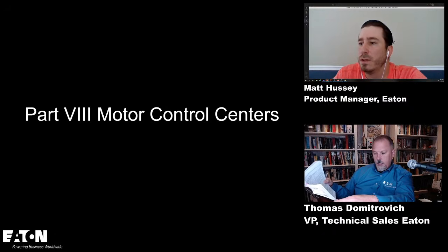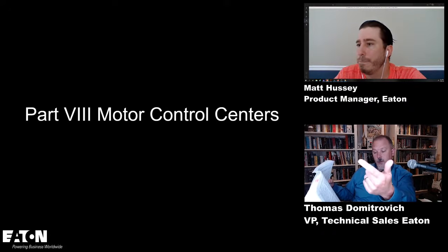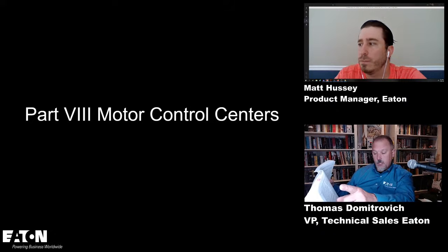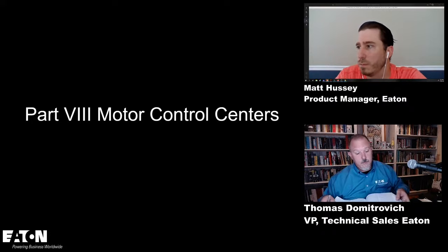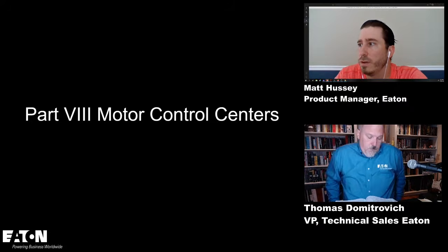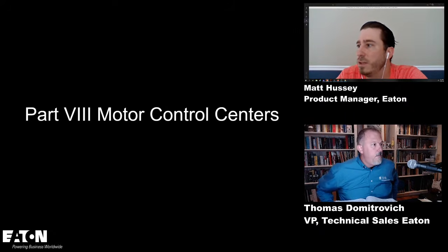Okay, cool. So they have to be provided with overcurrent protection. We're going to be talking about that in accordance with Parts 1, 2, and 8 of Article 240. So it points us back to 240 for overcurrent protection. It talks about the ampere rating and settings. We've got 430.95, service equipment. So we could have a motor control center as service equipment. Is that right? Yeah, you can get a service entrance MCC. Sweet. And we're going to talk about that too, right? Because we have the line side barrier issues that we have to think about, and a few other things.